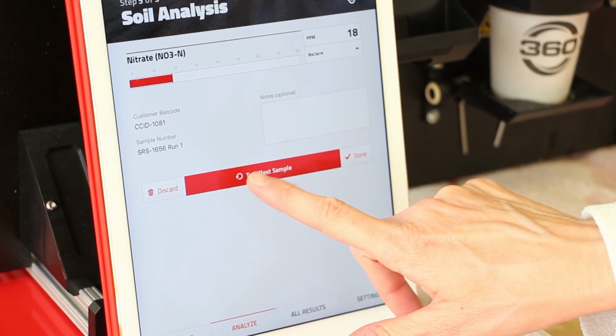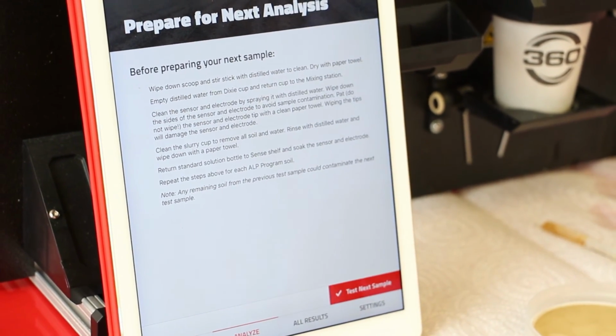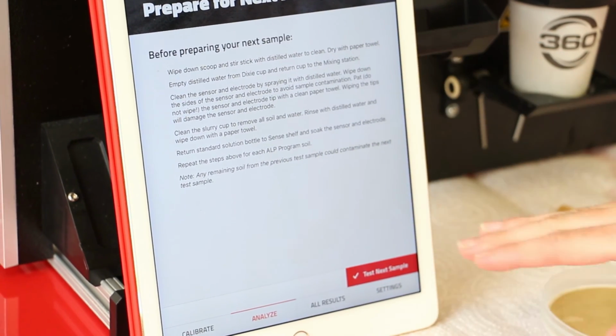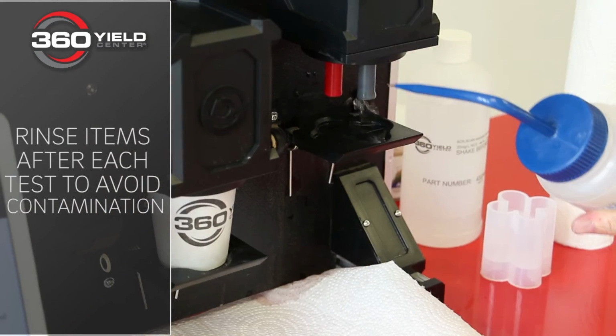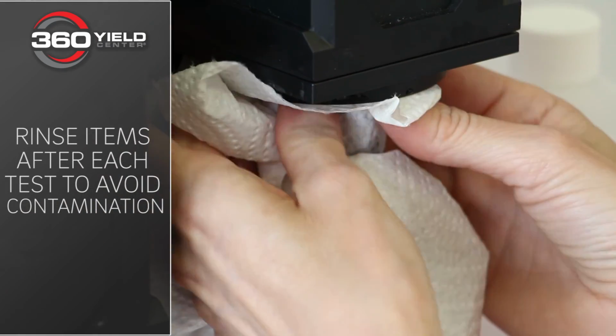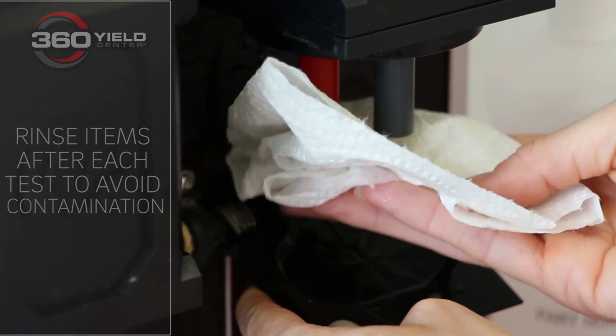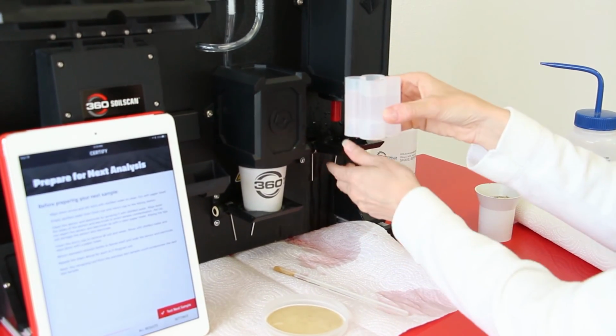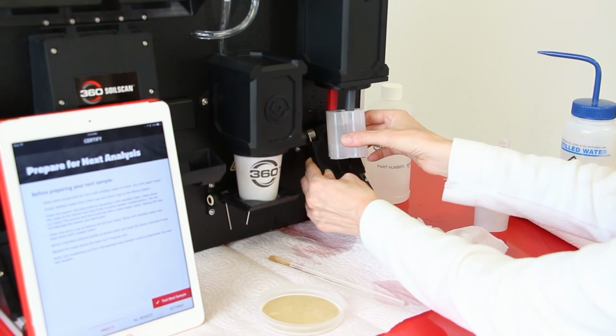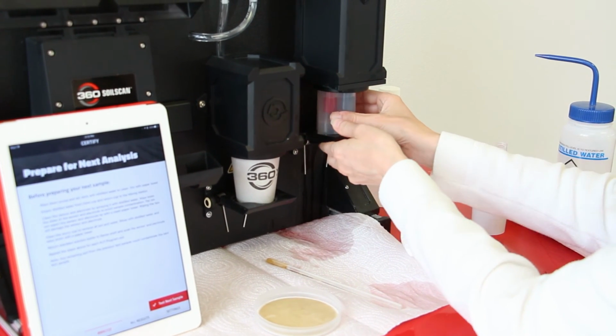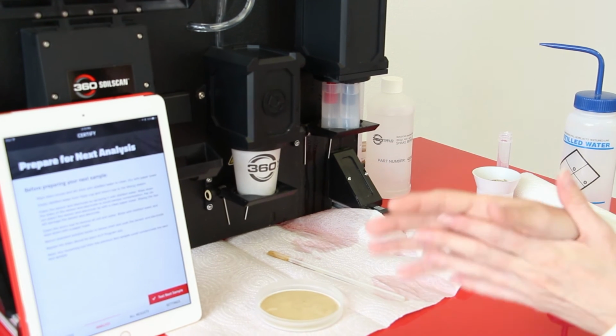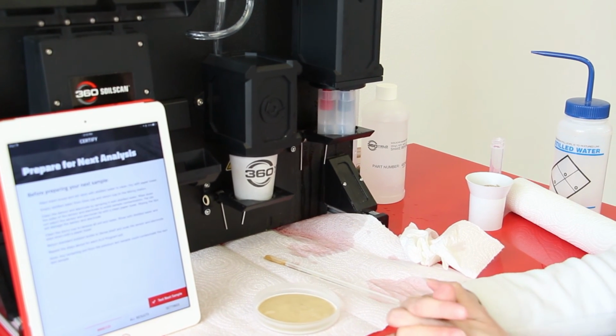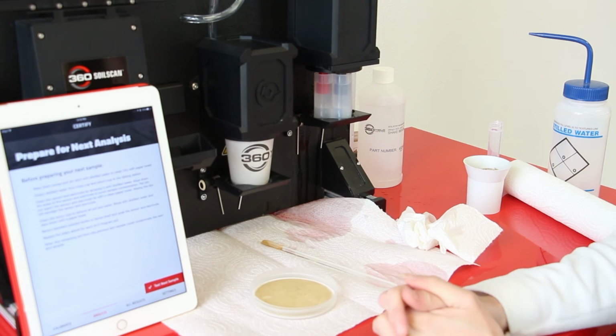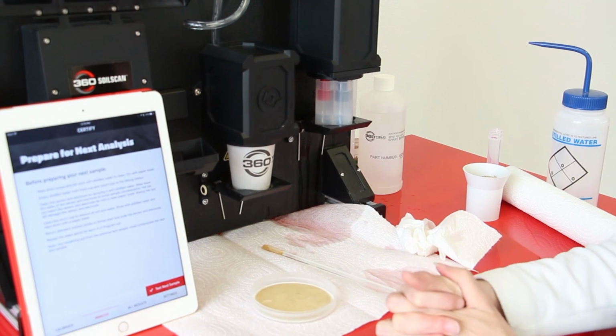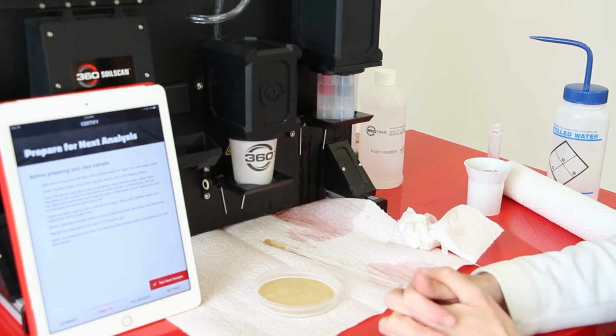Now we're going to press test the next sample. And this will give you all of your information that you need to prepare for your next sample. So what you want to do is remove your slurry cup and rinse everything back down with distilled water again. And return the standard solution in the calibration bottle back so the sensors are soaking on it. You do want to have that calibration bottle on when you are testing, because every time that we hit and mix the sample, the sensors are recalibrating themselves for their accuracy.